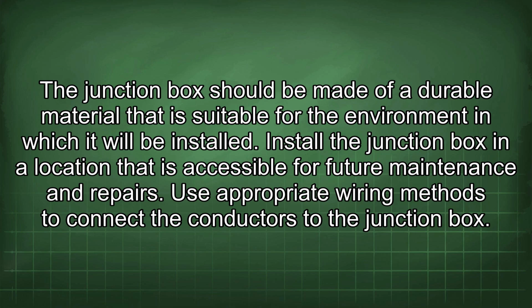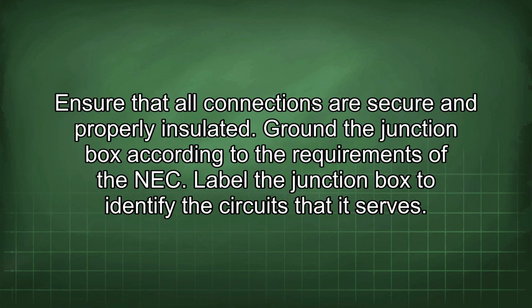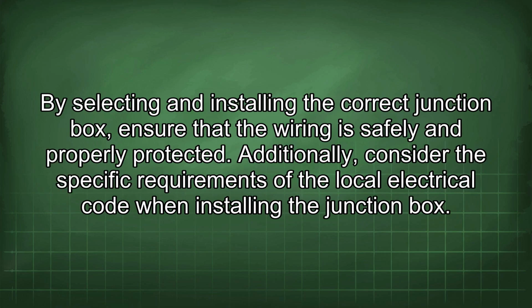Use appropriate wiring methods to connect the conductors to the junction box. Ensure that all connections are secure and properly insulated. Ground the junction box according to the requirements of the NEC. Label the junction box to identify the circuits that it serves. By selecting and installing the correct junction box, ensure that the wiring is safely and properly protected.